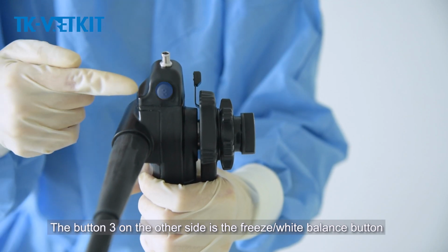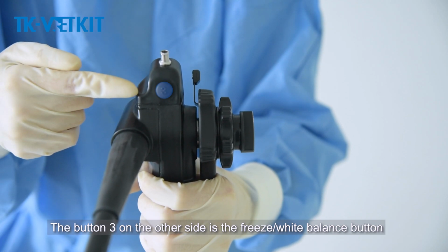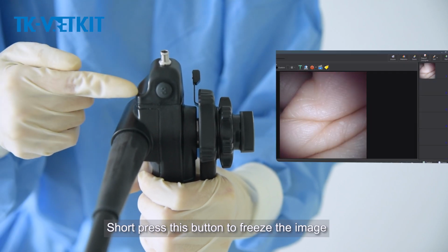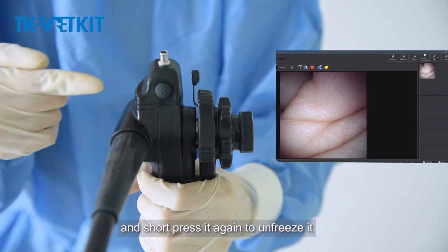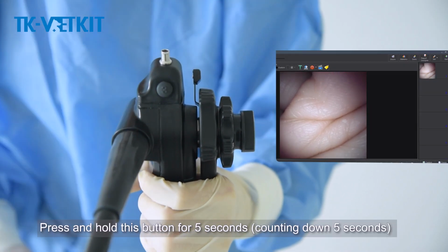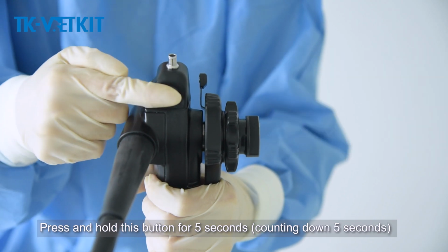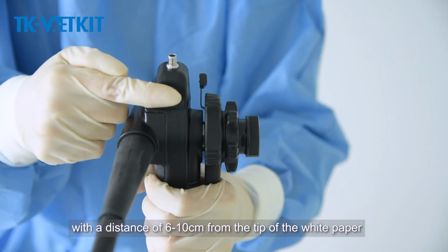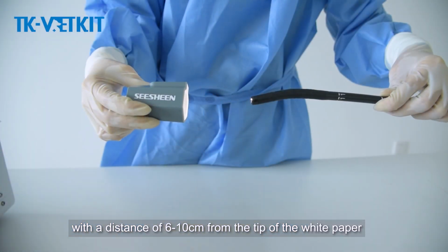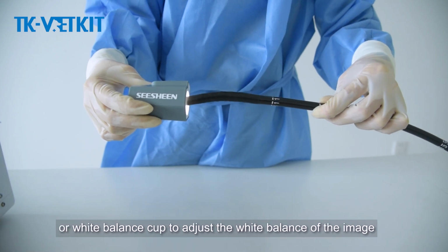The button 3 on the other side is the freeze/white balance button. Short press this button to freeze the image, and short press it again to unfreeze it. Press and hold this button for 5 seconds, counting down 5 seconds, with the tip at a distance of 6 to 10 centimeters from white paper or a white balance cup, to adjust the white balance of the image.